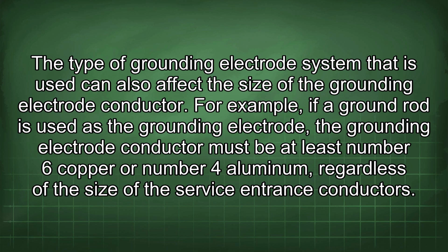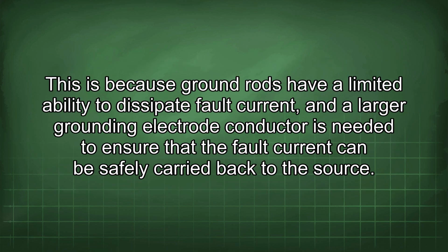The type of grounding electrode system that is used can also affect the size of the grounding electrode conductor. For example, if a ground rod is used as the grounding electrode, the grounding electrode conductor must be at least number 6 copper or number 4 aluminum, regardless of the size of the service entrance conductors. This is because ground rods have a limited ability to dissipate fault current, and a larger grounding electrode conductor is needed to ensure that the fault current can be safely carried back to the source.